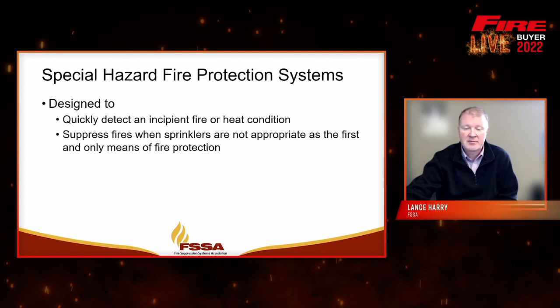In many cases these types of systems are used in conjunction with a sprinkler system, mostly because codes, particularly here in the US, require you to install sprinkler systems in most occupied buildings. That doesn't necessarily give you the kind of protection you want in high value asset areas. So many end users elect to install a special hazard system along with the sprinkler system in order to detect the fire early and try to suppress it before a sprinkler system might even go off.